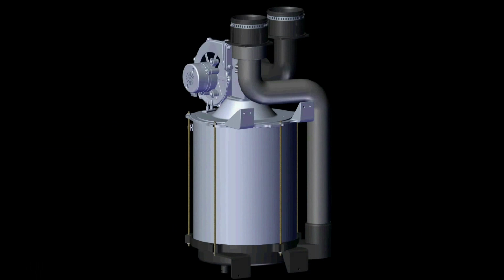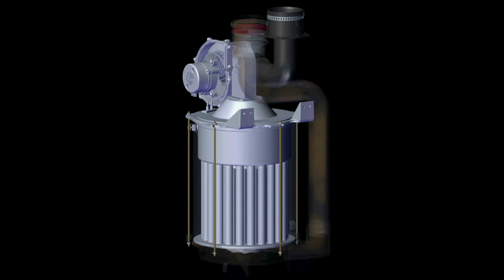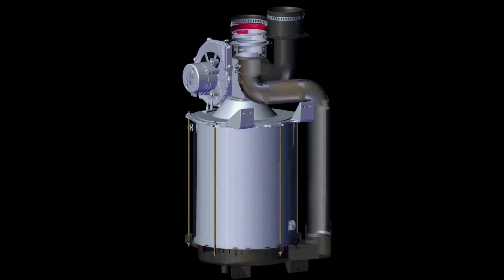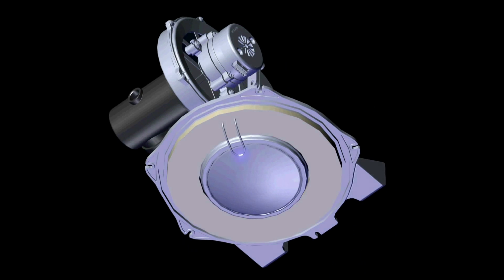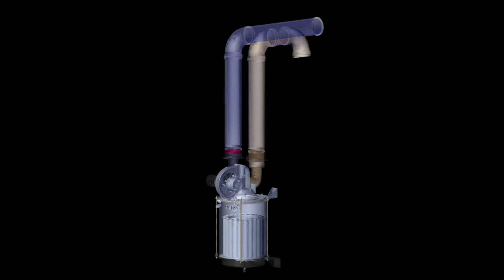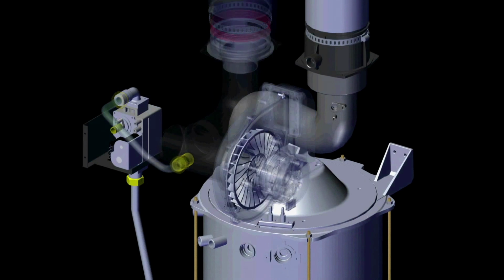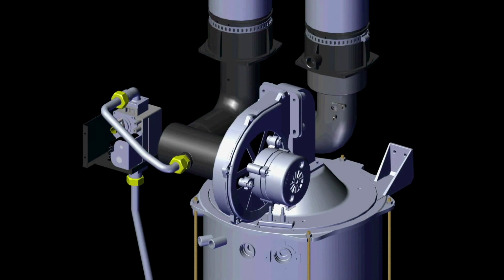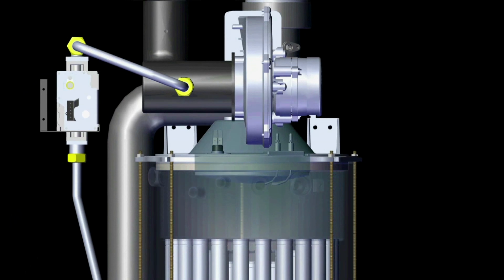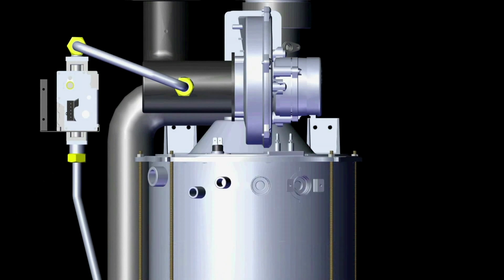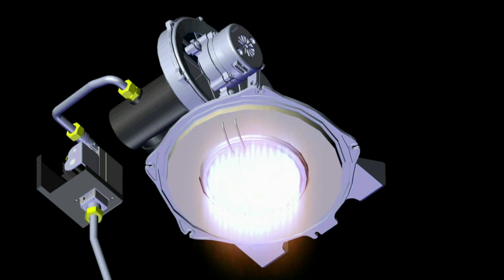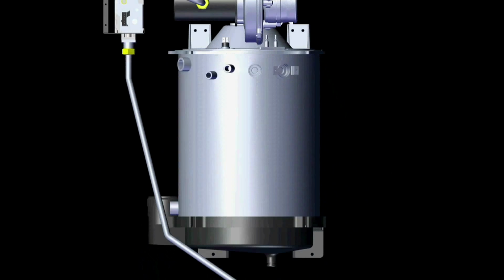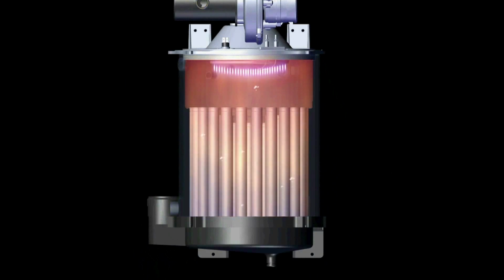Pre-purge for emitting residual exhaust gas is proceeded with blower action for 3 seconds. Power is supplied from the ignition transformer to the spark electrode to ignite the fuel. Now you can see the process in which air is moved into the combustion system and flue gases are discharged to the outside. The blower operates and the gas valve opens, sending a mixture of gas and air which enters the burner. The mixed gas enters inside the burner. At this time, the entered mixed gas and air are ignited with spark ignition system. If the flame is sensed and the flame is not extinguished after 2 seconds, the boiler operates normally.